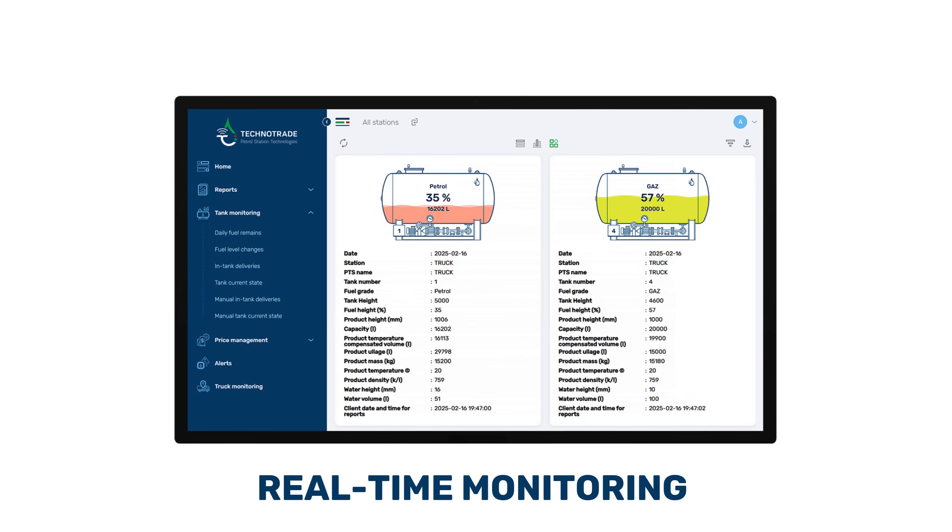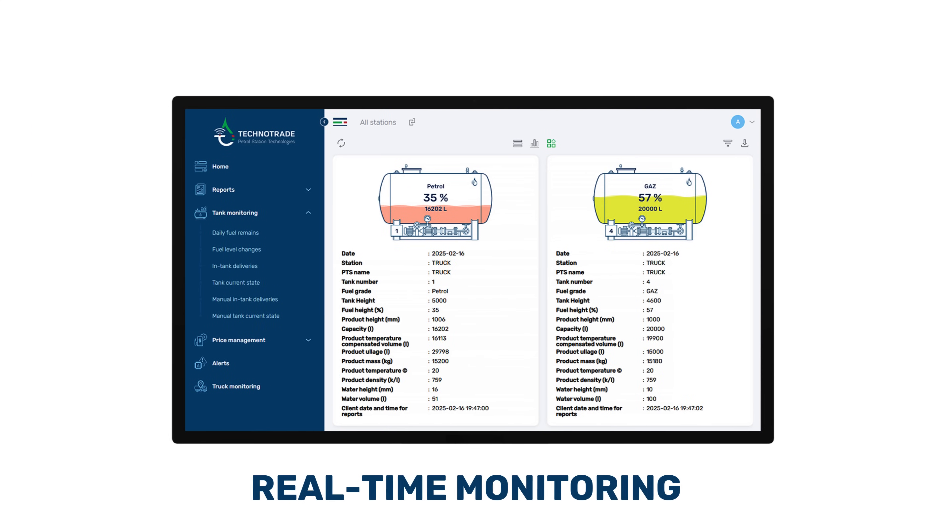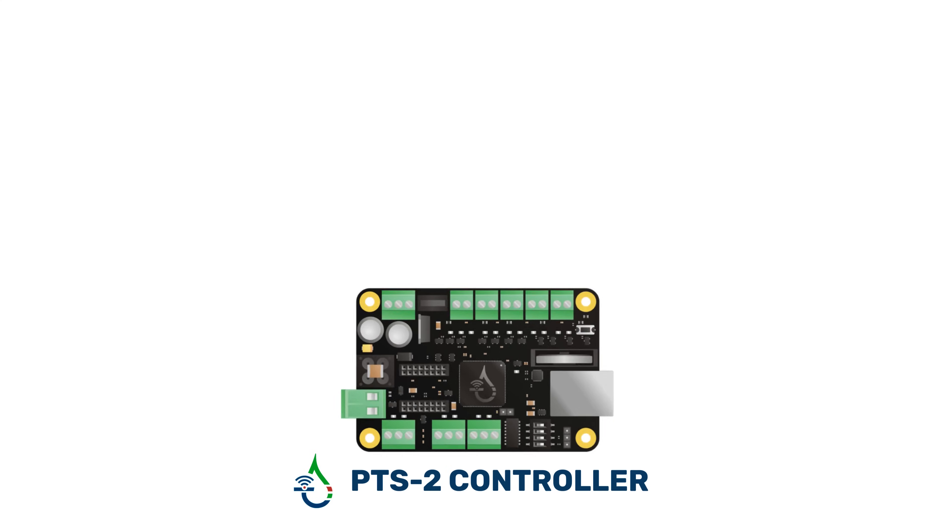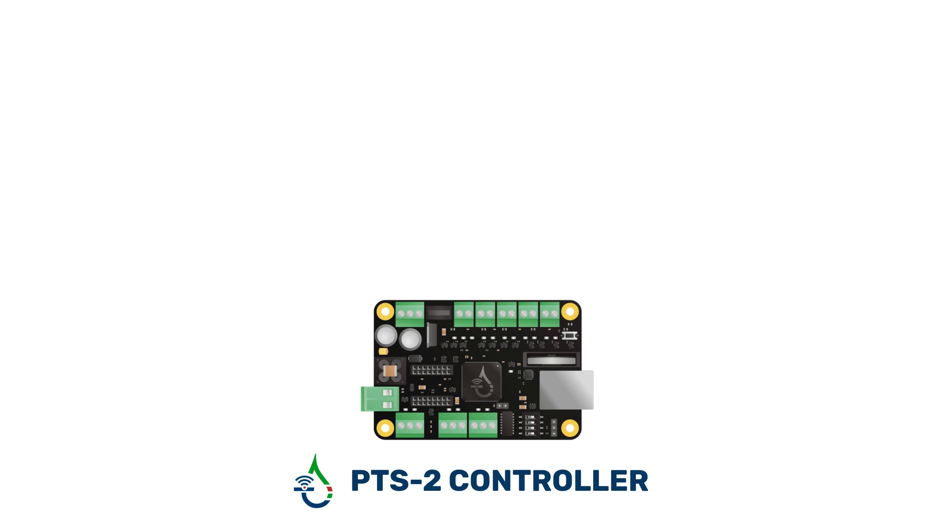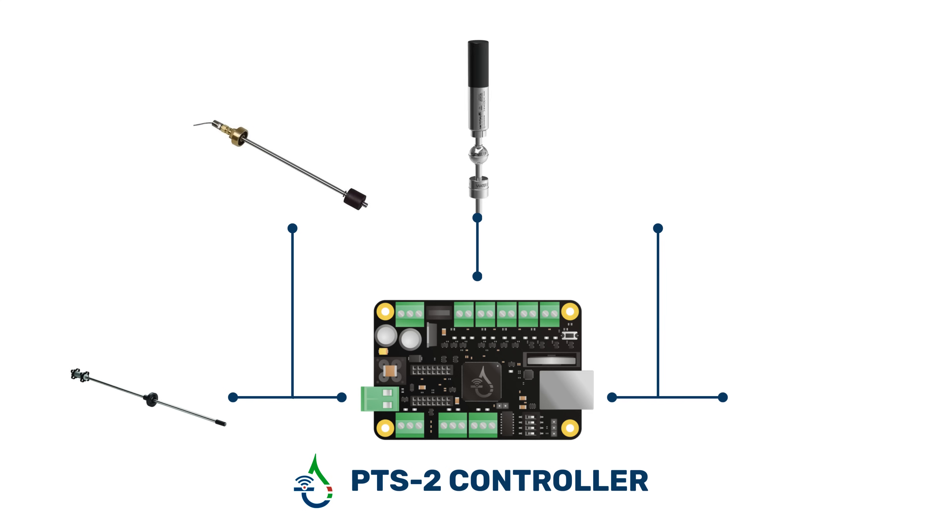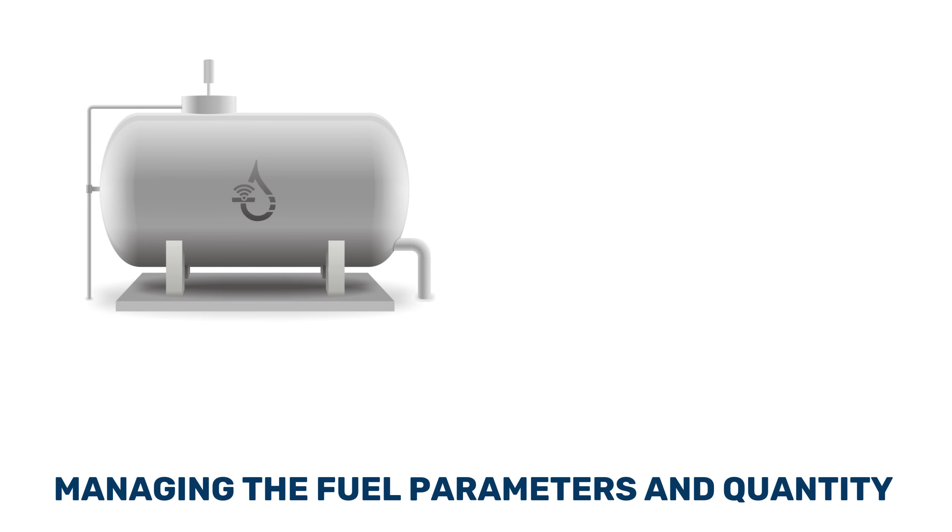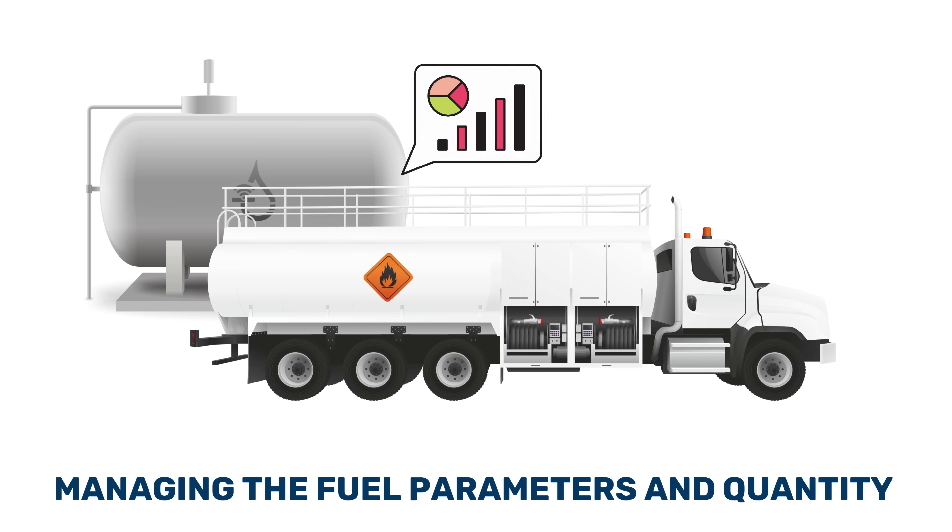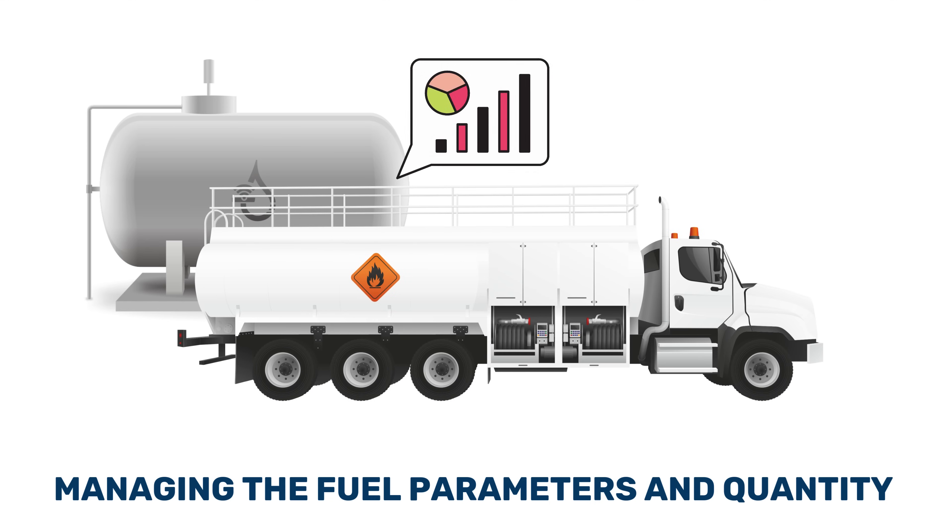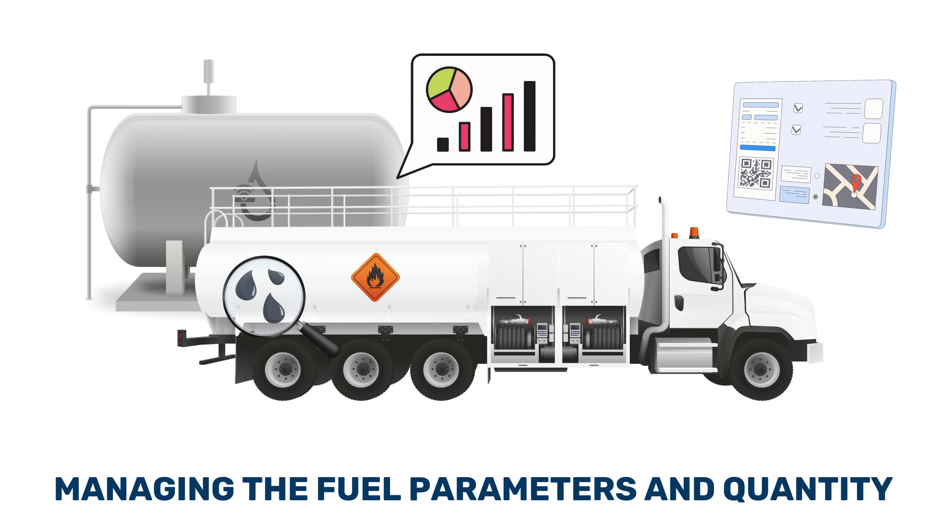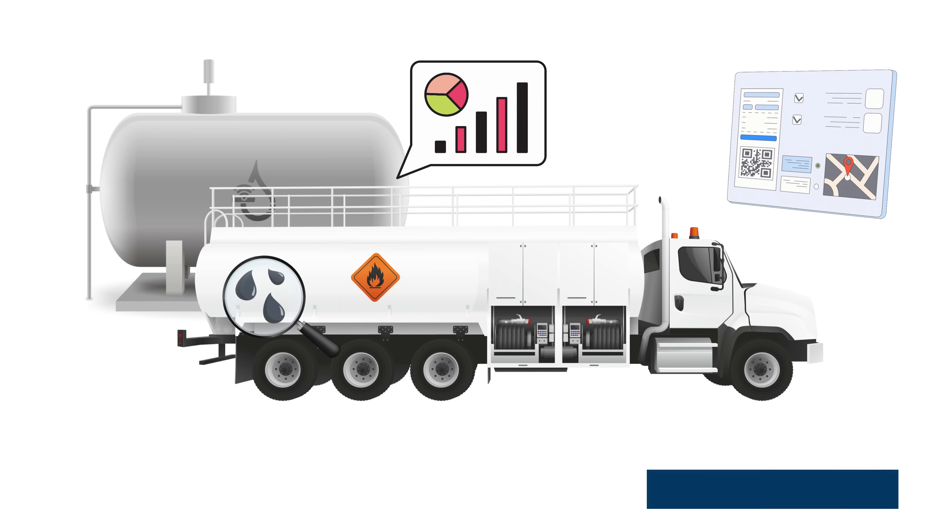This arrangement enables real-time monitoring of the current fuel volume and activity. The PTS2 controller is compatible with the majority of level sensor brands installed inside the tanks. This enables managing fuel parameters and quantity in tanks by utilizing tank calibration charts and detecting in-tank deliveries and leakages from the tanks.